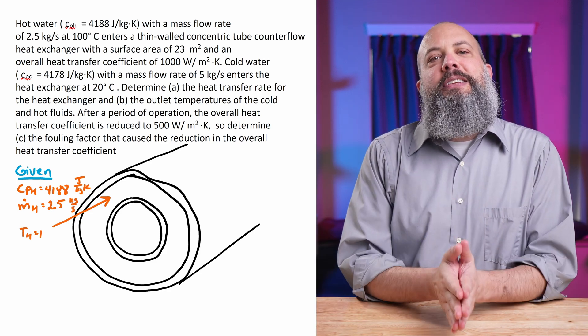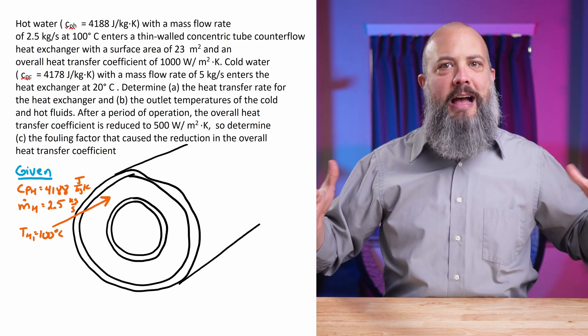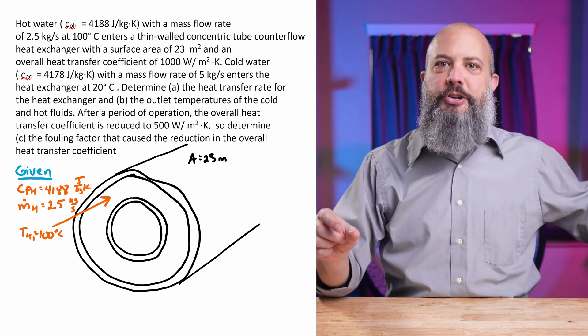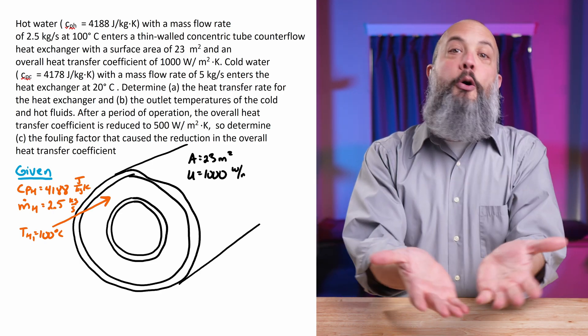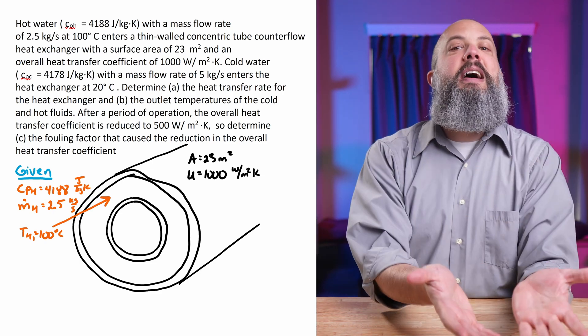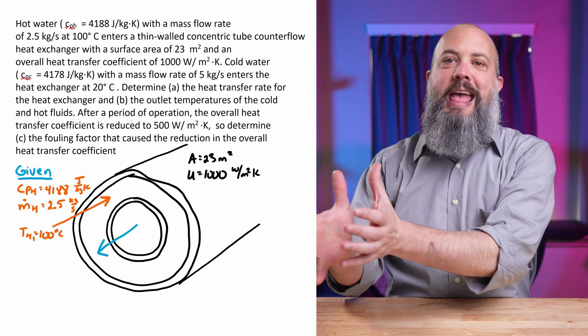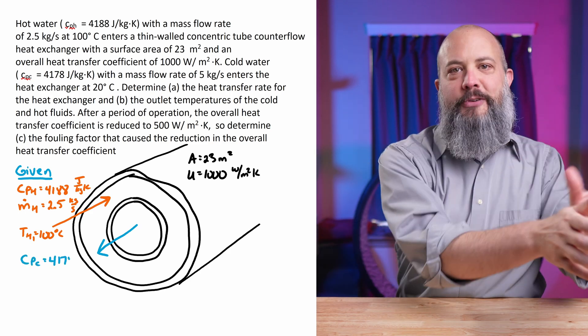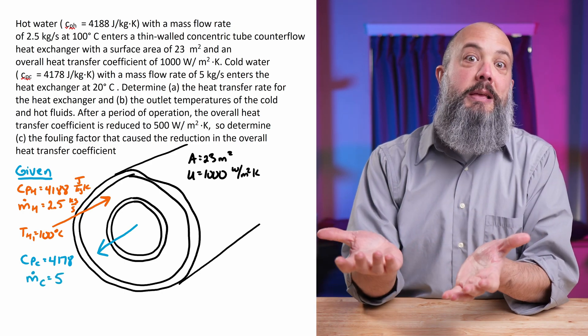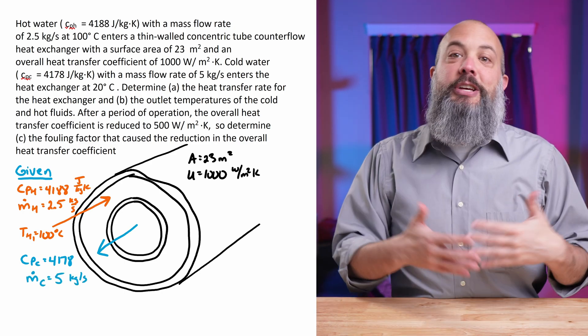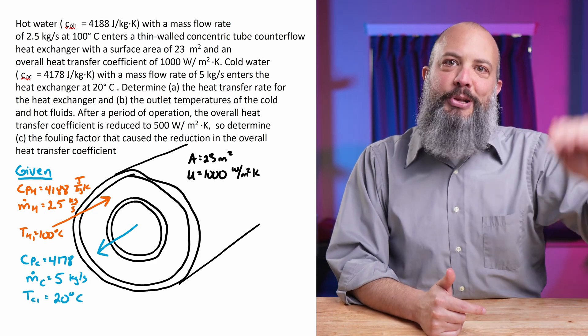NTU effectiveness is used when you're trying to decide what heat exchanger to buy. You have your system, you know your cold inlet temperature and your hot inlet temperature, and you have your mass flow rates, but you don't know what outlet temperatures are going to be. For different models of heat exchangers, you know UA for one exchanger and UA for another, and you're trying to figure out which one to buy based on exit temperatures or temperature limits.